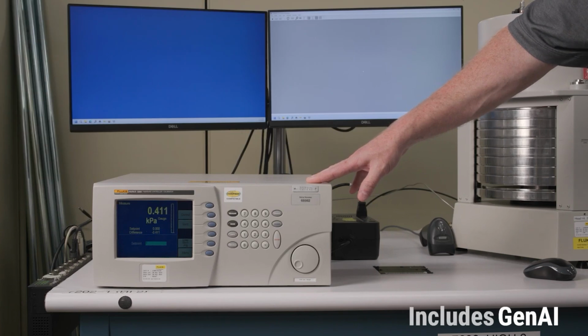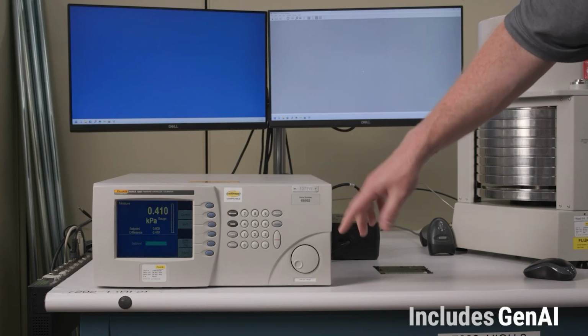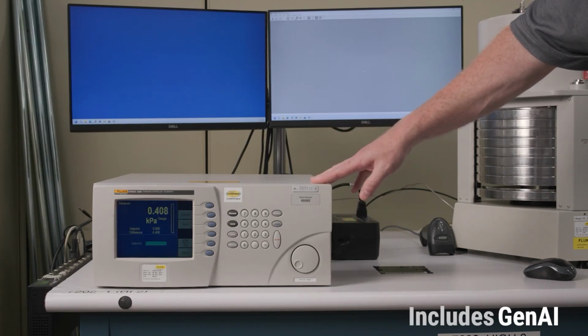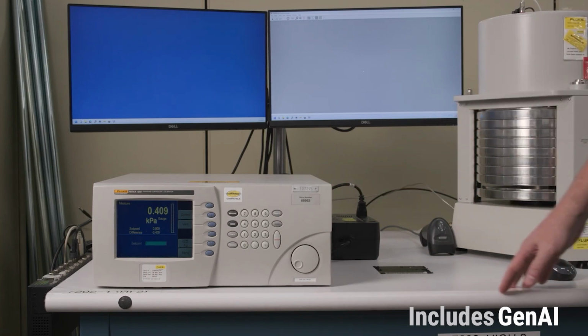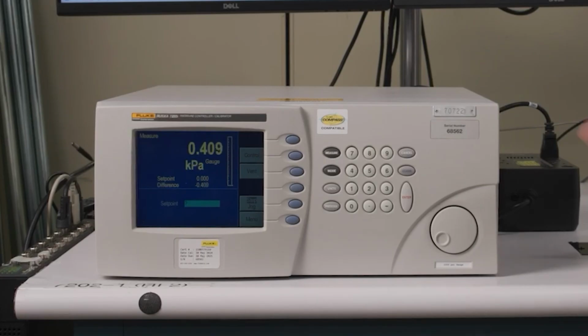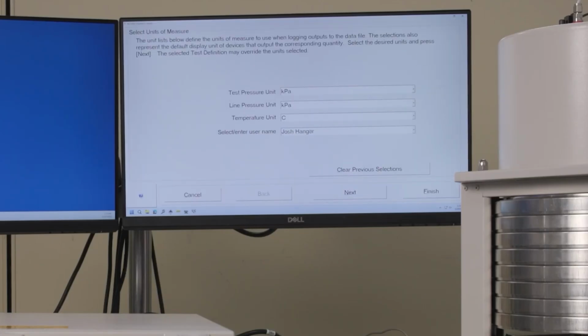Today, we're going to go through how to run a pressure calibration using a piston gauge and Compass pressure software to calibrate the 7250 pressure calibrator. To start, we connect the test line to the device under test, or DUT. For this demo, the DUT is rated to a full-scale pressure of 1000 psi.